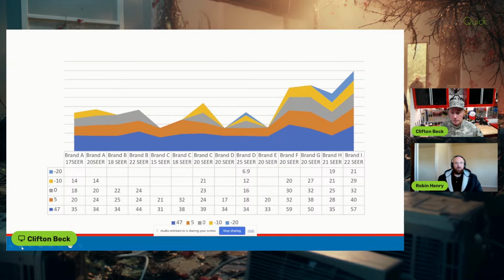We have a heating-dominated climate here, so AC comes into the mix but it's predominantly heating. So we definitely want that base pan heater and cold climate capability. Nobody wants their heat pump to tap out at 5 degrees like you mentioned - you want that wiggle room going down to -13, -20. That's a very important consideration, and it goes back to what you said: heat pump A will be awesome here but completely irrelevant over there. It's something to take into consideration.